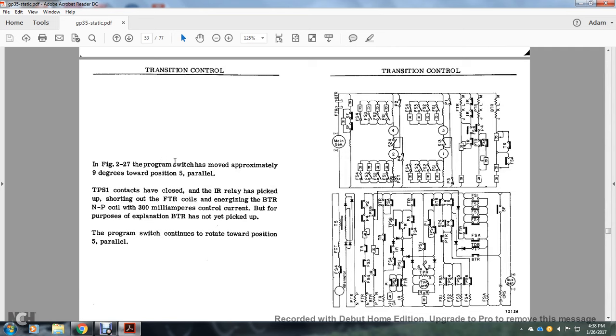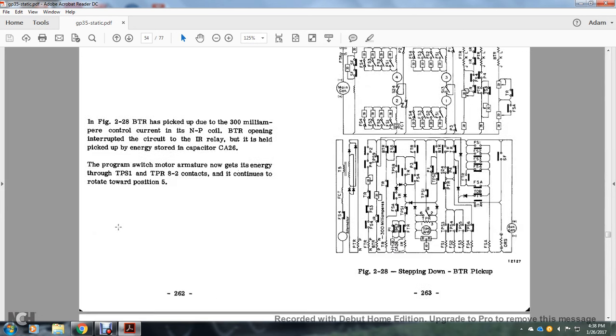In figure 27, the program switches approximately 9 degrees toward position 5 of the parallel. The transition power switch 1 contact has closed. The interrupting relay has picked up and shorted out the front transition relay coils, energizing the back transition relay at NP, which continues to rotate toward position parallel 5. In figure 28, the back transition relay has picked up due to the 300 milliamperes control current. The NP coil of the back transition relay opened the circuit of the interrupting relay, but it is held with the pickup of the energy stored in capacitor CA26.